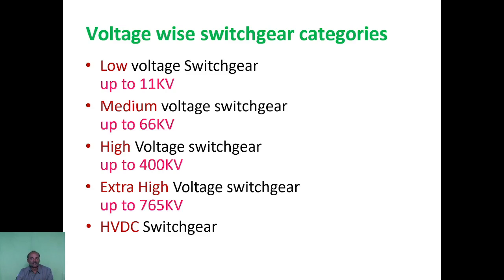According to the voltage levels we are using, we have different types of switchgear. Low voltage switchgear, that is up to 11 kV. Medium voltage switchgear up to 66. High voltage, 66 up to 400 kV. Extra high voltage switchgear is used for voltage levels up to 765 kV. And beyond that, for extra high voltage and ultra high voltage, we are using HVDC switchgear.